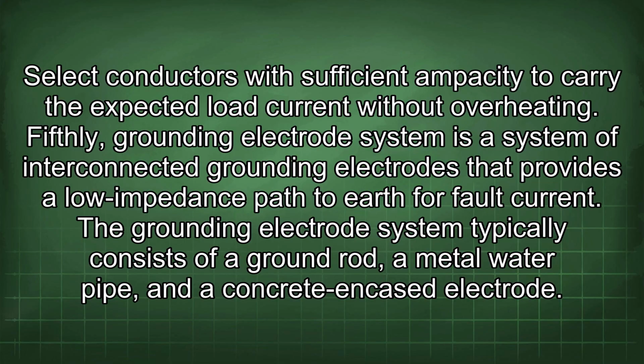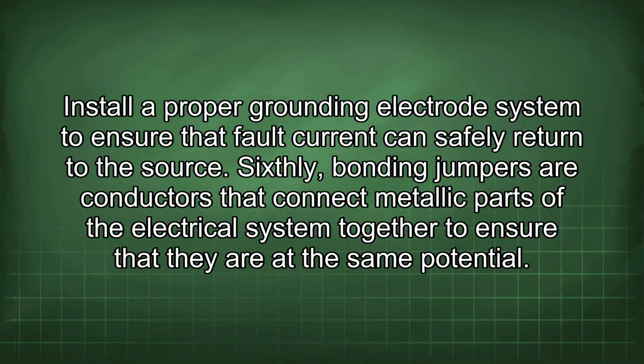Fifthly, grounding electrode system is a system of interconnected grounding electrodes that provides a low impedance path to earth for fault current. The grounding electrode system typically consists of a ground rod, a metal water pipe, and a concrete encased electrode. Install a proper grounding electrode system to ensure that fault current can safely return to the source.